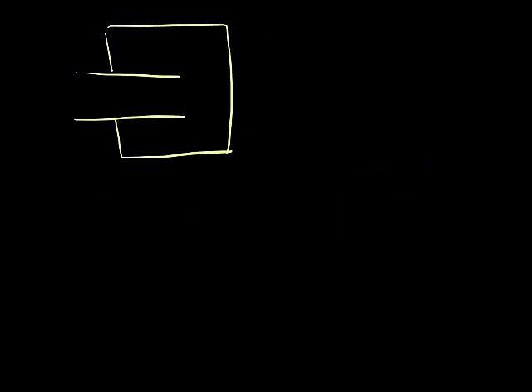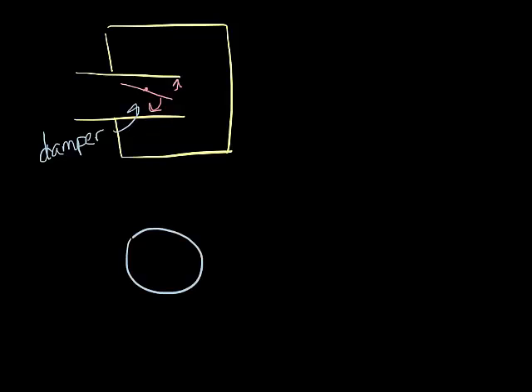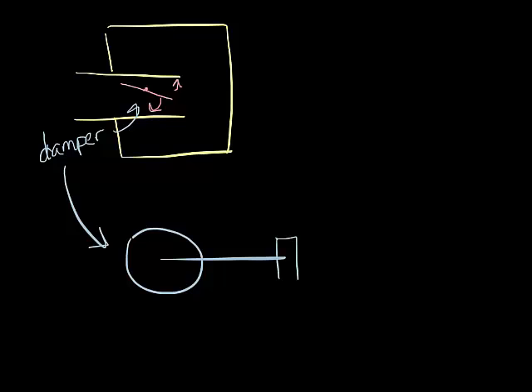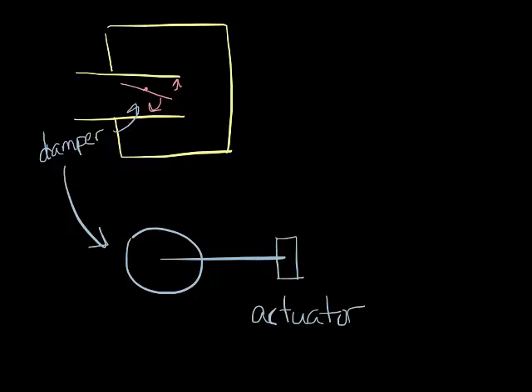Inside the inlet is a damper that opens and closes to control how much air can go through the box. This damper is mounted on a shaft that goes into a control box. At the end of the shaft, inside the control box is an actuator that has a motor that rotates the shaft to open and close the damper.